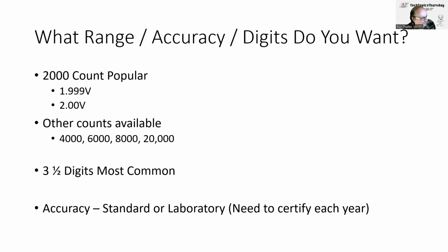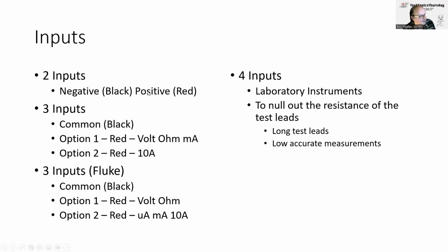The other thing is to look at your inputs. You may have a positive and negative input, or three inputs: a common, a red used for volts, ohms, and milliamps, and a special one for the 10 amp circuit. This is most common for most meters. The Fluke seems to be a little different - it has a black one, a red for measuring volts and ohms, and a second red for measuring microamps, milliamps, and 10 amps. Then you get some laboratory instruments with actually 4 leads, so you can null out the resistance of your test leads and get more accurate measurements.